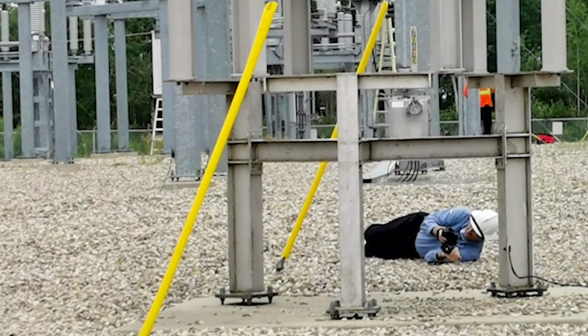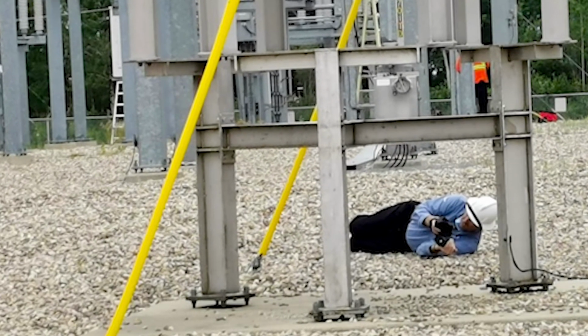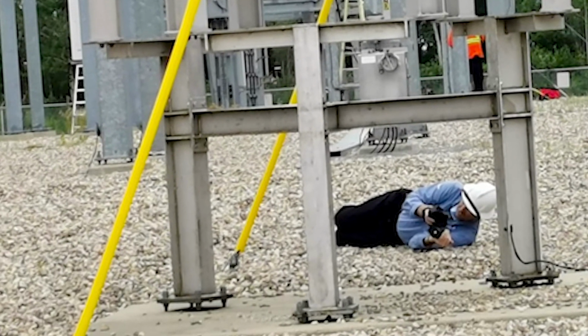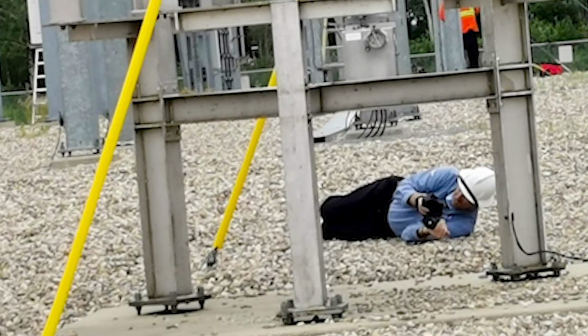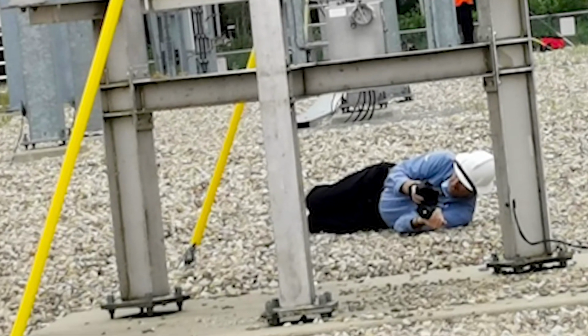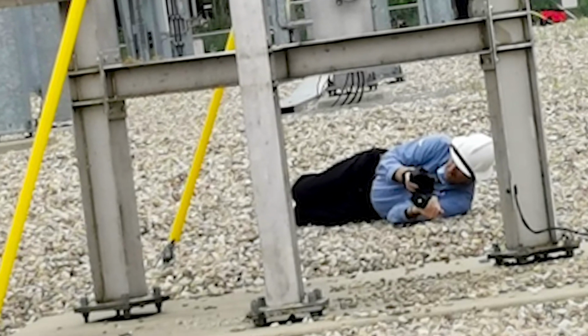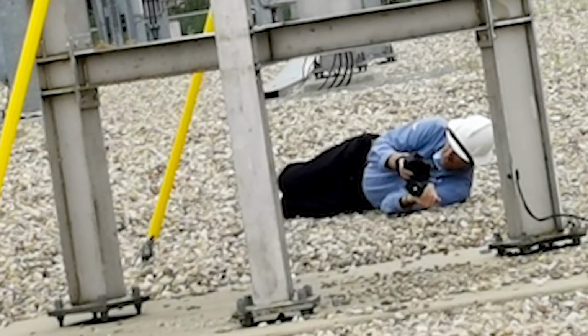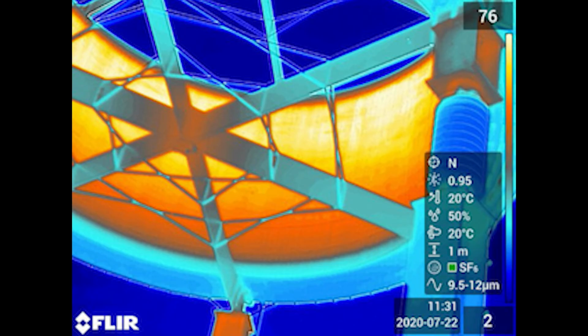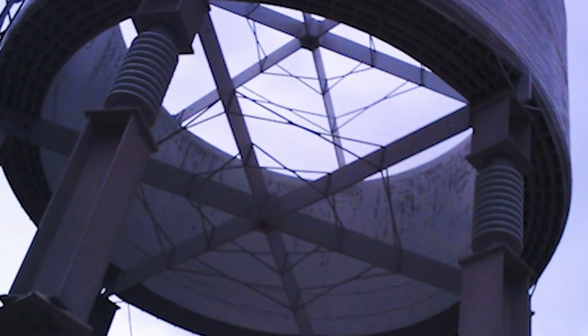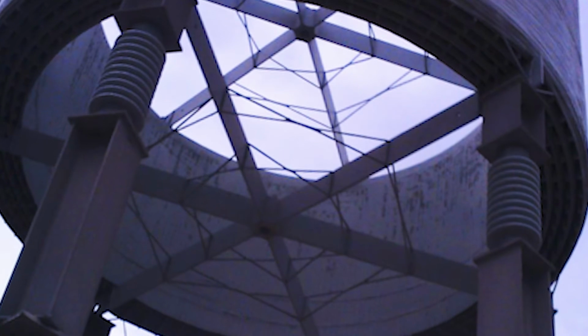Here Elton Hunter was laying on the ground when this and the following 3 images were taken. Sometimes you have to get down and underneath and take a look at the equipment from different angles. You have to look at things from 2 or 3 different sides to make sure you can see everything. This is what Elton saw when he was laying down on the ground. He was looking up inside the reactor for hot spots or cold spots inside and anything unusual. This is a full spectrum picture from on the ground looking up. Once again, looking for anything unusual, any contaminants that might be on the outside, and documenting anything that we might see from that perspective.